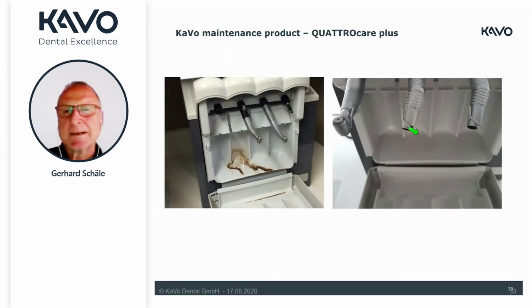This is how it looks. We just placed incoming instruments, for example, into the inside of a QUATTROcare, and you see what happens now. Yeah, after the cleaning process, but this is an extraordinary sample for an instrument. Basically, if the cleaning is done correctly, most of the oil particles will be shown like in a spot like here.